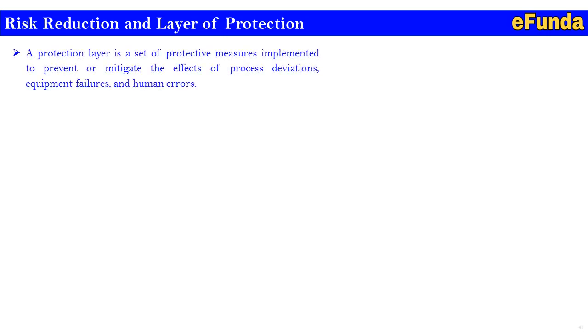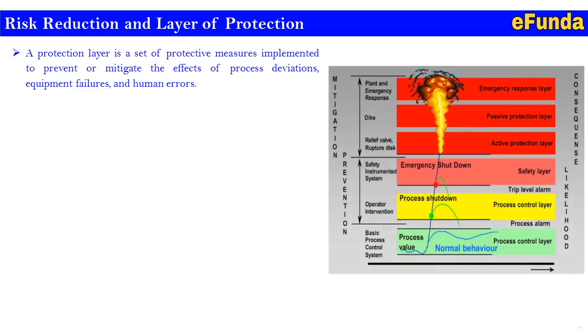For better understanding of a Safety Instrumented System or Emergency Shutdown System, we follow a structured sequence. Risk reduction and layers of protection: a protection layer is a set of protective measures implemented to prevent or mitigate the effect of process deviations, equipment failure, and human error. The layers include process control, process alarm, trip-level alarm, safety layer, active protection layer, passive protection layer, and emergency response layer.